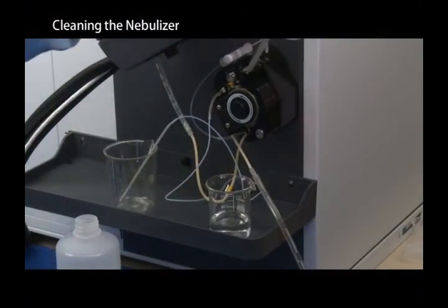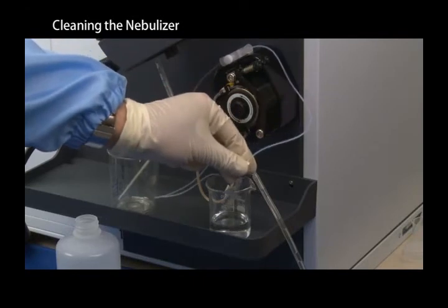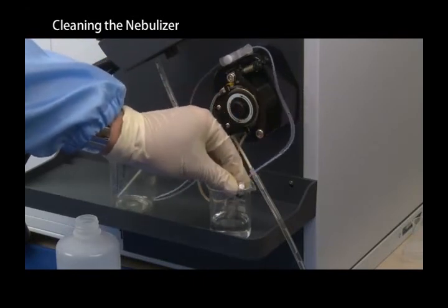Reverse the peristaltic pump tubing for the sample on the peristaltic pump, then place the tip of the nebulizer in pure water.